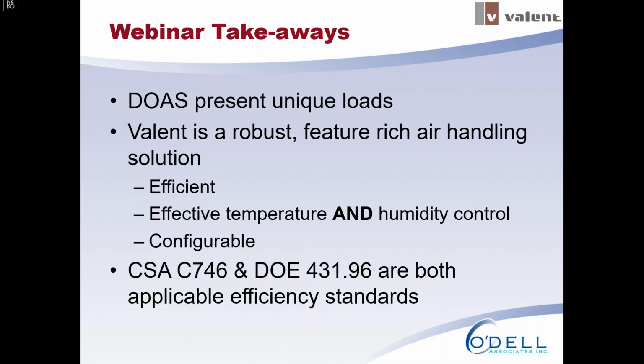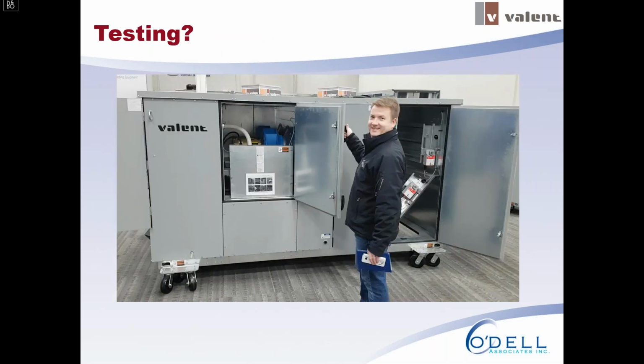So what are some of the key webinar takeaways? We're getting near the end here. DOAS presents unique loads. Brian went through that and talked about humidity control, heating and cooling, and wide varying loads, and the importance of having a product that can address those items well. Valent has a robust and feature-rich air handling solution. It can provide effective temperature and humidity control, is very configurable to meet a lot of demands, and the last point is that CSA C746 and DOE 431.96 are both applicable energy standards in Ontario.